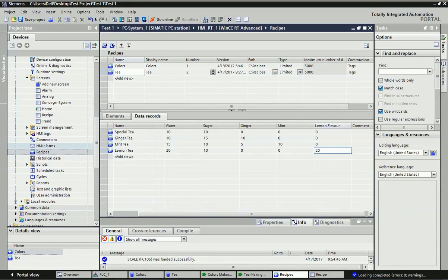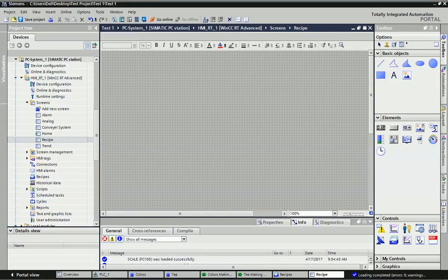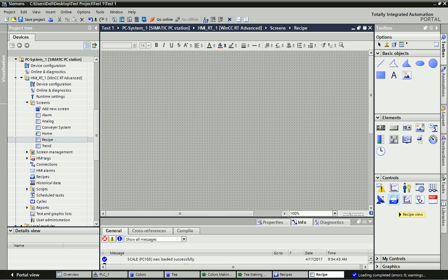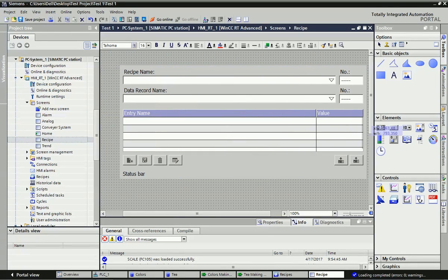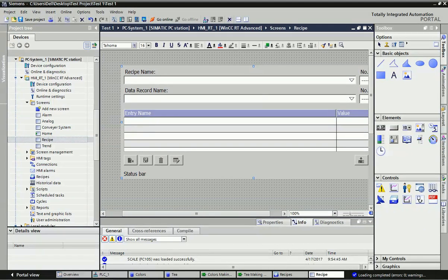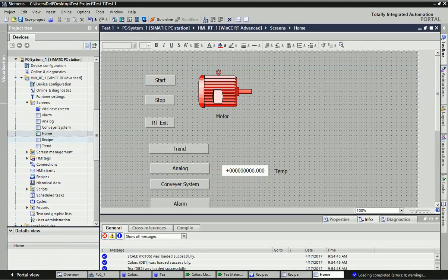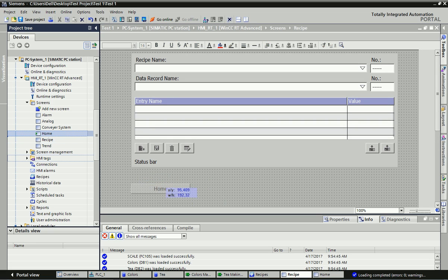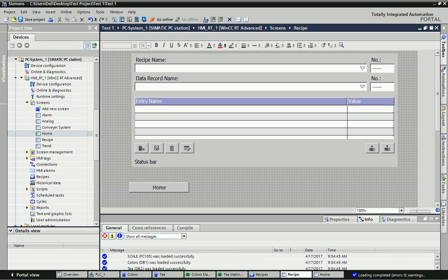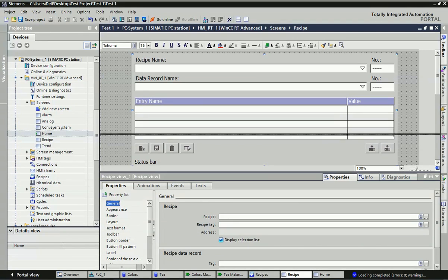After adding the elements and data records, we will go to the Screen. I have added one screen and renamed it 'Recipe'. In the blank window, we will take a Recipe View. From the Controls, you will get a Recipe View option. You just drag and drop it and you will get this window. From this window we can see everything in runtime. I will also take a navigation button from the home screen - I already have the Recipe button. I will also drag a Home button and set it for navigation.